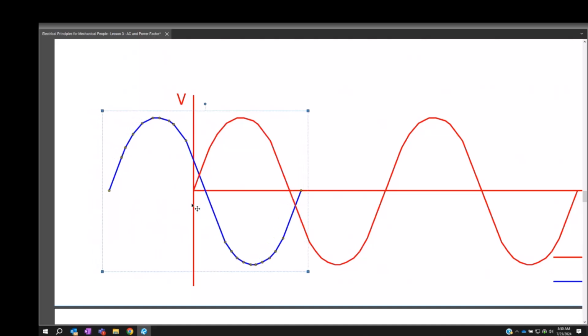As I slowly push that curve back, say to a power factor of 0.2, that motor's not going to have much power. It won't be able to turn much torque. So that 20 horsepower motor at this point is more like a 1 horsepower motor.